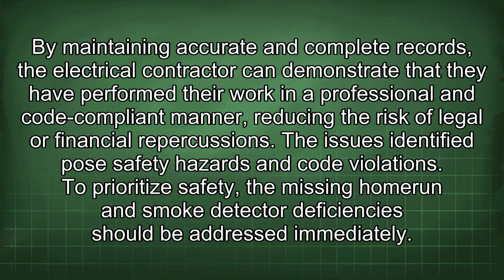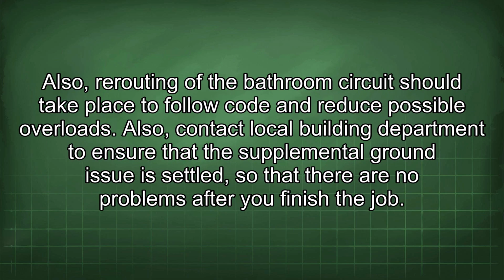The issues identified pose safety hazards and code violations. To prioritize safety, the missing home run and smoke detector deficiencies should be addressed immediately. Also, rerouting of the bathroom circuit should take place to follow code and reduce possible overloads. Also, contact the local building department to ensure that the supplemental ground issue is settled, so that there are no problems after you finish the job.